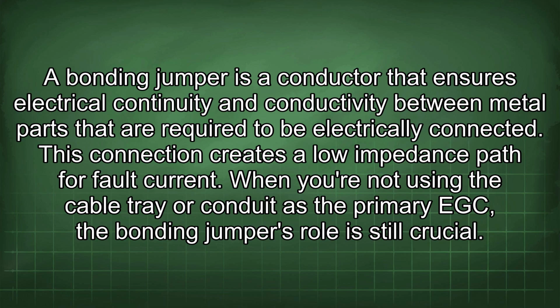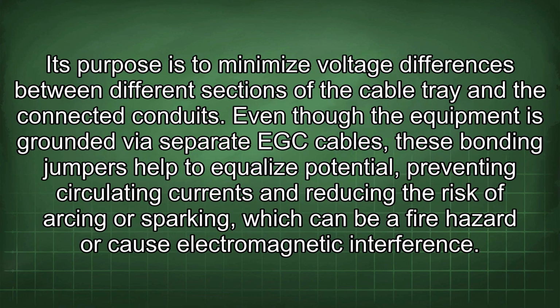A bonding jumper is a conductor that ensures electrical continuity and conductivity between metal parts that are required to be electrically connected. This connection creates a low impedance path for fault current. When you're not using the cable tray or conduit as the primary EGC, the bonding jumper's role is still crucial. Its purpose is to minimize voltage differences between different sections of the cable tray and the connected conduits. Even though the equipment is grounded via separate EGC cables, these bonding jumpers help to equalize potential, preventing circulating currents and reducing the risk of arcing or sparking, which can be a fire hazard or cause electromagnetic interference.